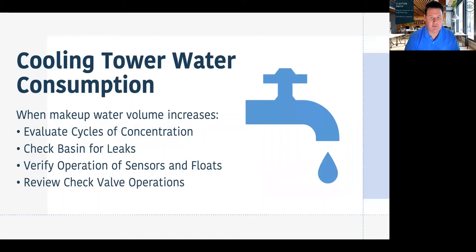Another major issue we have from our chiller plant optimization is cooling tower water, right? We see makeup water volume increases and we just kind of throw water in. There's so much water being used in our cooling towers. When we see that volume increase happen, we want to go down through a checklist as well. First, evaluate your cycles of concentration, making sure your chemistry is right. We're managing not just the cycles of concentration and the chemistry of the water, but also, if you do have deduct meters on that makeup water, that you're evaluating that meter as well. I just had an issue today where our municipality, one of our hospitals, basically eliminated all of our sewer credits for our makeup water meters because the meters were wrong and we weren't validating and managing those meters. So it hit us in the pocketbook.